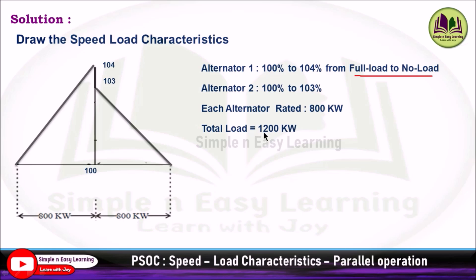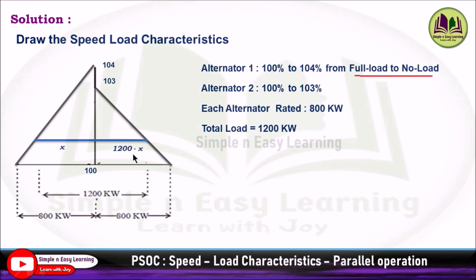The two alternators, alternator 1 and alternator 2, each have a rated capacity of 800 kilowatt. The total load of 1200 kilowatt is shared between them. To represent this, draw a line in between the two speed regulation curves. Consider alternator 1 sharing a load of x and the remaining load shared by alternator 2, that is 1200 minus x. This is the point where both alternators share the load, and the frequency at which the load is shared is h. The points are labeled using alphabets: A, B, C, D, E, F, H, G.